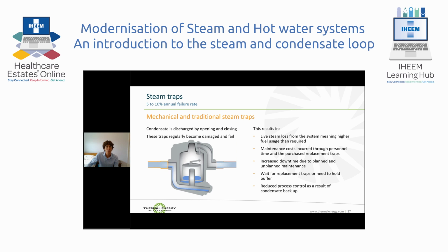The problem with these mechanical steam traps is that these opening and closing devices are operating several times a minute in hot, dirty environments, many thousands of times a year. That contributes to a 5 to 10% annual failure rate. When these steam traps fail, they either fail closed, inhibiting heat transfer, or fail open, wasting valuable live steam which hasn't condensed and contributed any useful energy to the system, allowing it to escape out of the system.